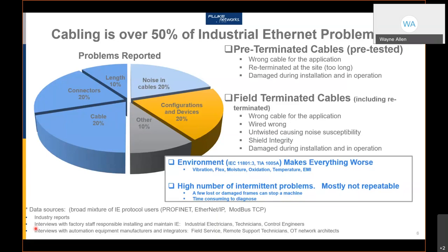Going back to where we were: cabling is over 50% of industrial Ethernet problems, whether pre-terminated or field-terminated. We are seeing problems with length, connectors, or the cable type being used. One of the key areas of problems is noise in the cables — and noise entering a cable could actually be a cabling problem itself, as I'll share later.